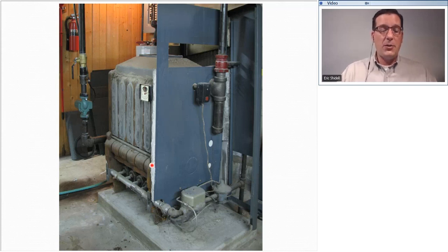When the manufacturer designed and built this boiler, they offered it in multiple sizes, multiple BTU ratings. So this boiler may have been available anywhere from, say, 75,000 BTU up to maybe 150 or 250,000 BTU. The only difference between the smaller size boiler and the larger size boiler is the number of sections that it is made out of. So this boiler here would be a 1, 2, 3, 4, 5, 6, or 7 section boiler. A smaller boiler may only have had 4 or 5 sections. A larger boiler may have 10 or 12 sections. So the number of sections that are bolted together really dictates the heating capacity of that boiler.